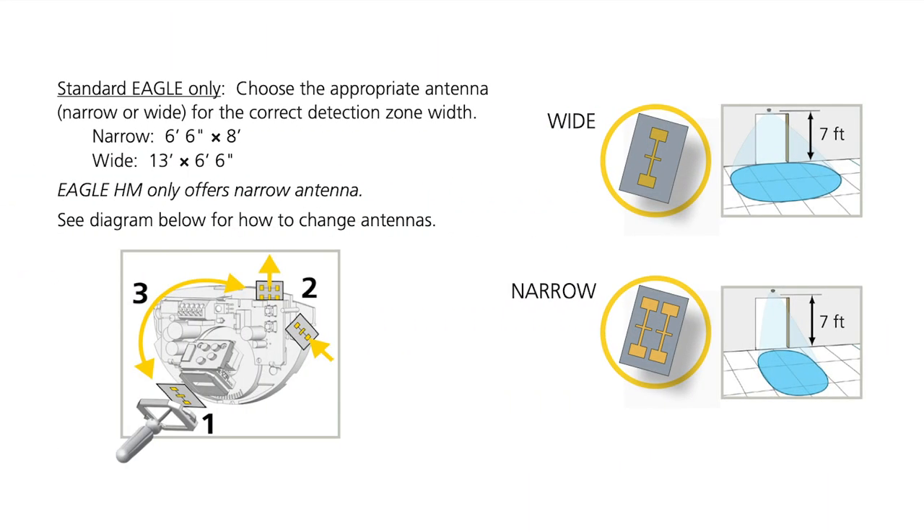For the standard EAGLE, choose the appropriate antenna for the preferred detection zone width. The wide antenna covers a detection zone of 13 foot by 6 foot 6 inches at a 7 foot mounting height. The narrow antenna covers a detection zone of 6 foot 6 inches by 8 foot at a 7 foot mounting height.